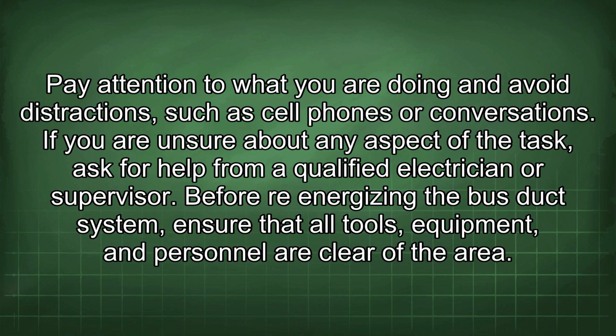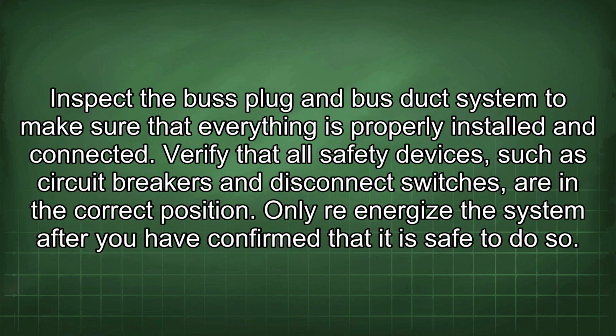Before re-energizing the bus duct system, ensure that all tools, equipment, and personnel are clear of the area. Inspect the bus plug and bus duct system to make sure that everything is properly installed and connected. Verify that all safety devices, such as circuit breakers and disconnect switches, are in the correct position. Only re-energize the system after you have confirmed that it is safe to do so.